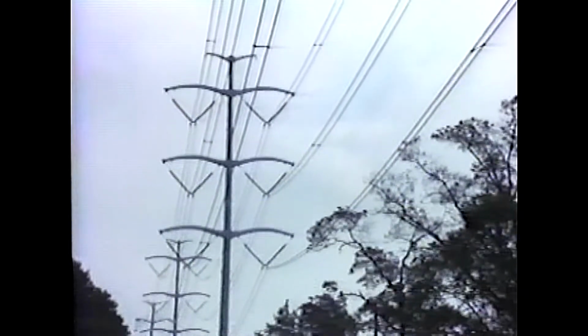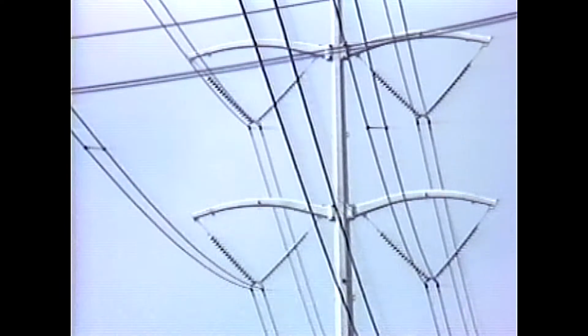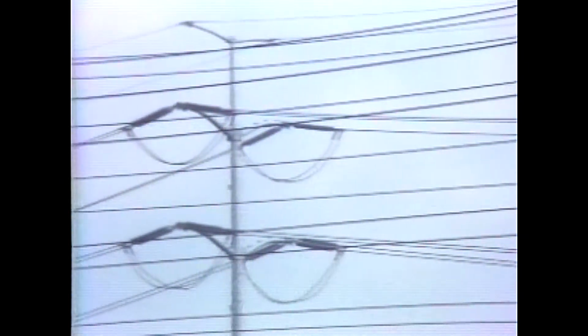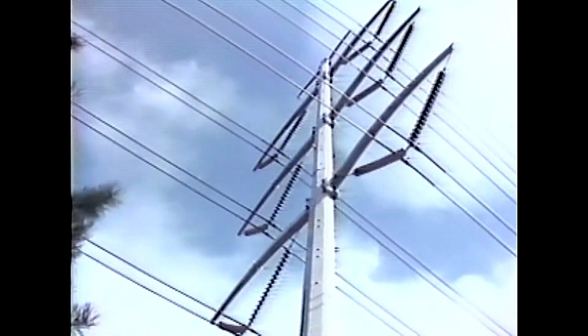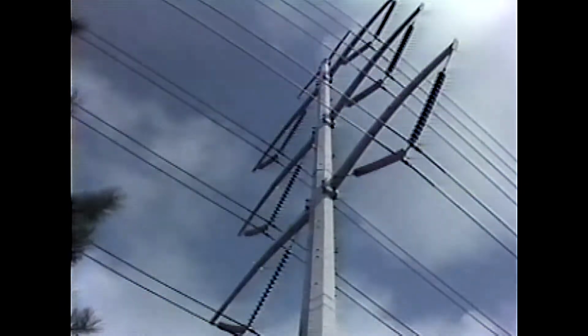In the early 1970s, engineers at Brookhaven National Laboratory pointed out that the use of superconducting cables would largely eliminate the limitation on length associated with conventional underground cables, and at the same time provide very high circuit power capacity in a relatively small diameter pipe with minimal impact on the environment. Virtually none of the technology existed at that time, and the first step was to develop suitable materials.